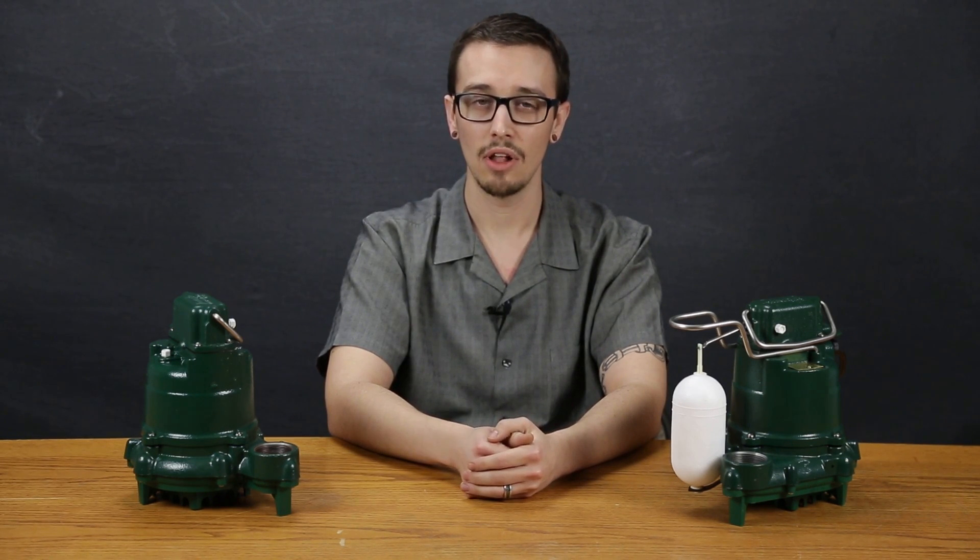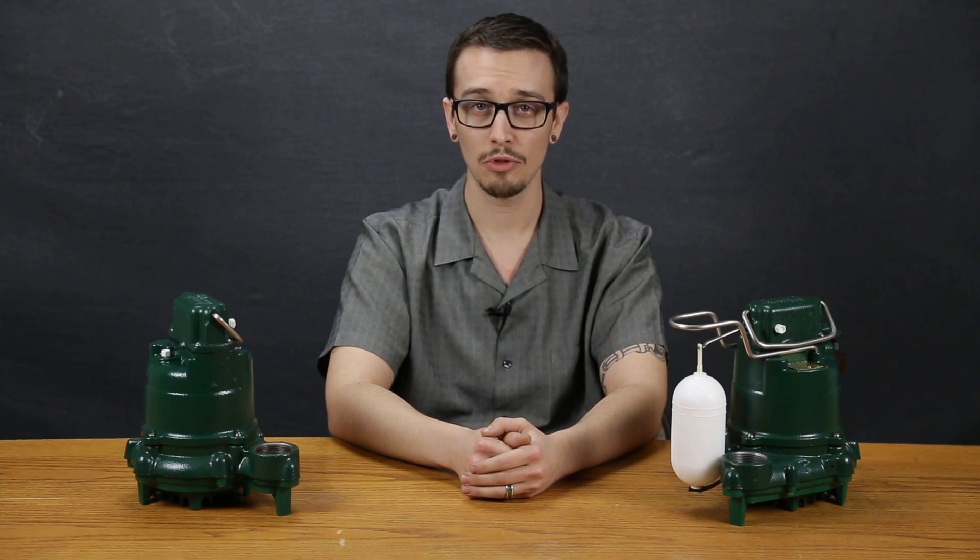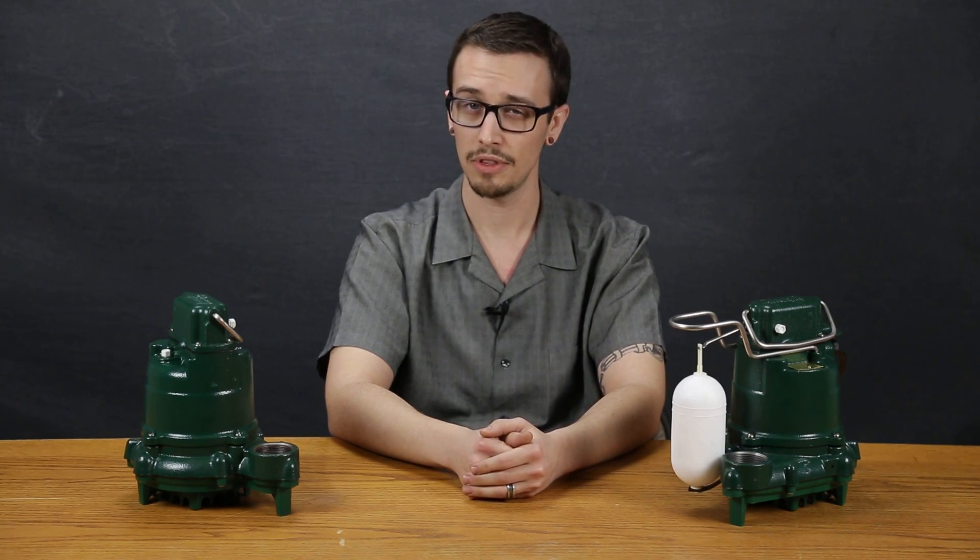With this in mind, Zoeller included a non-clog vortex impeller, which reduces the chances of it becoming clogged or getting bound. A vortex impeller by design is further away from any solid that enters the volute to minimize the possibility of impact or contact of the material being pumped. For optimal life, it's best to avoid pumping solids with this pump.